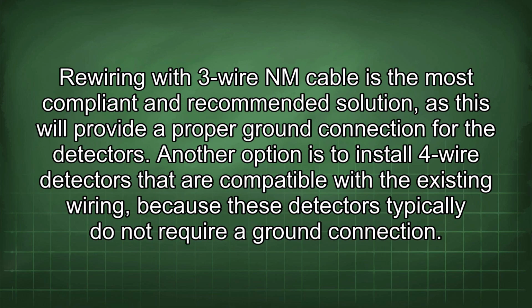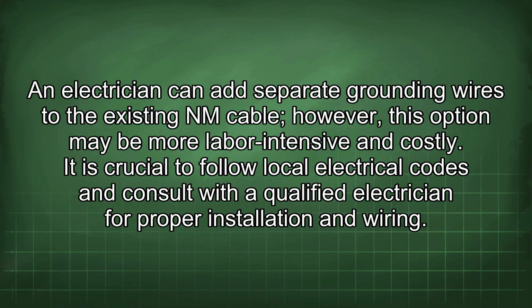Rewiring with 3-wire NM cable is the most compliant and recommended solution, as this will provide a proper ground connection for the detectors. Another option is to install 4-wire detectors that are compatible with the existing wiring, because these detectors typically do not require a ground connection. An electrician can add separate grounding wires to the existing NM cable, however, this option may be more labor-intensive and costly. It is crucial to follow local electrical codes and consult with a qualified electrician for proper installation and wiring.